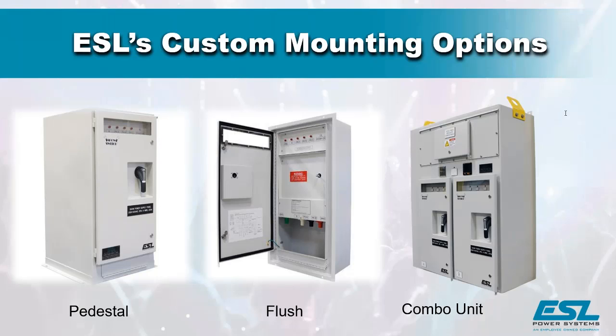So yes, the front door is interlocked to the circuit breaker. It doesn't technically prevent the door from being opened until the circuit is off—rather, you just can't gain access to anything live unless the door is closed. You cannot access any live parts at any time when the door is open, because it's interlocked to the circuit breaker. In that center picture, that unit's dead. Over on the left picture, the unit's live, assuming the handle is engaged all the way.